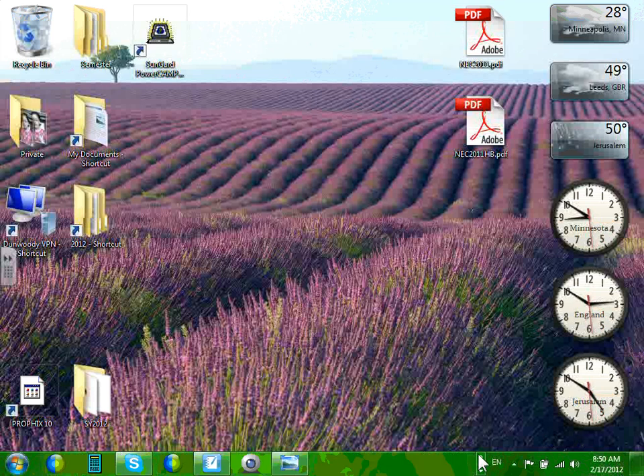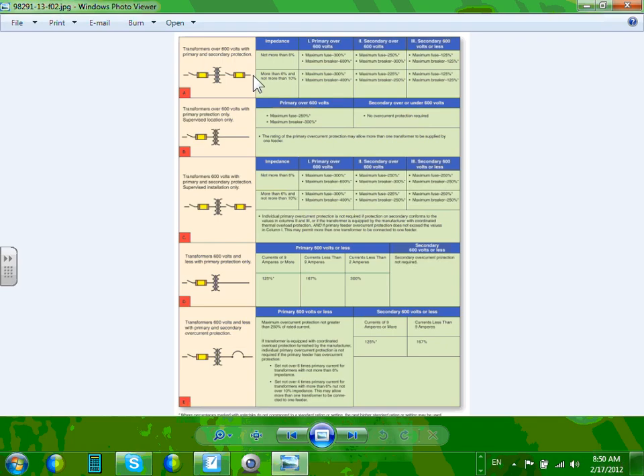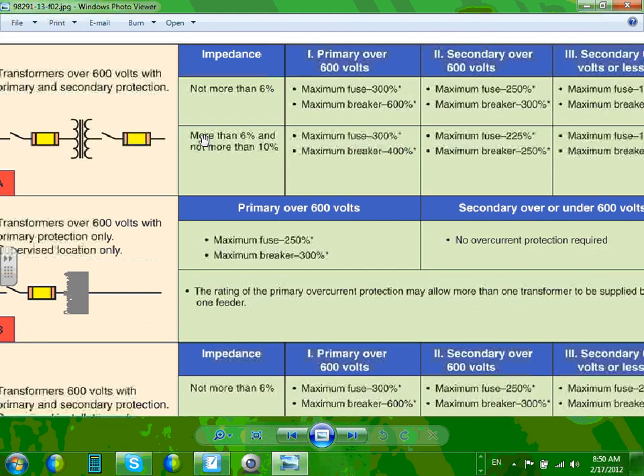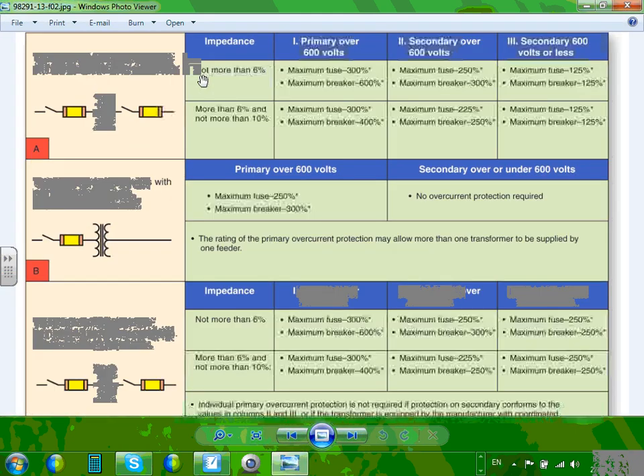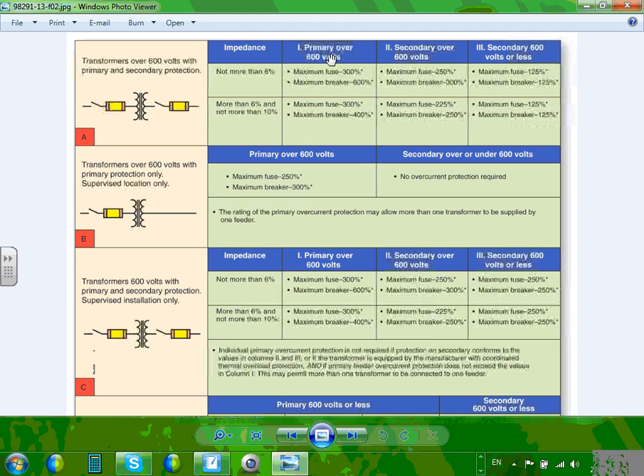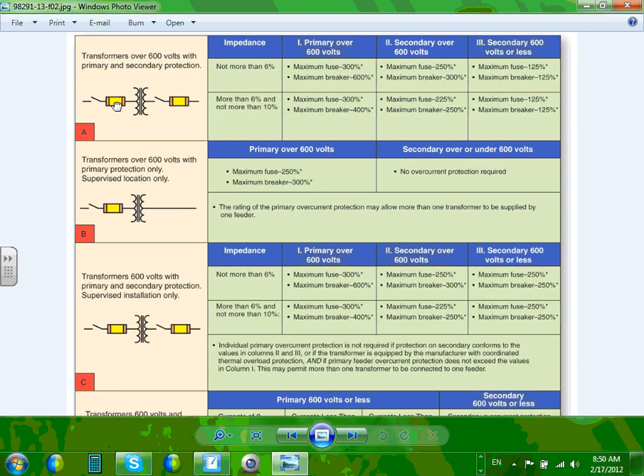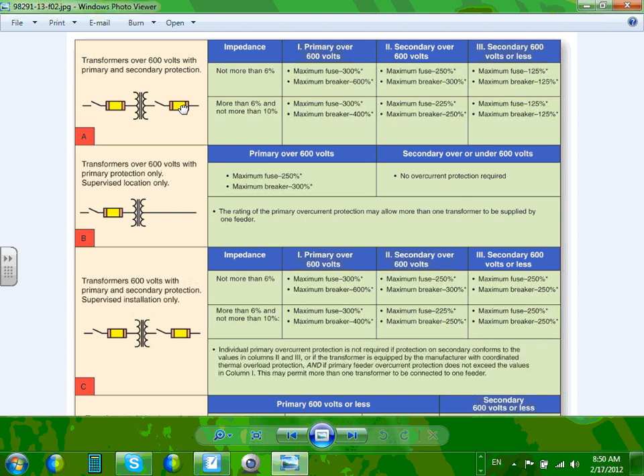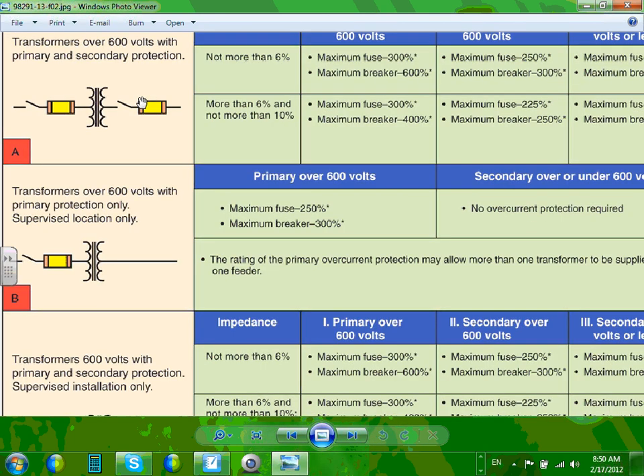While it's powering here. So while it's powering, guys, I want to bring to your attention, when we have a transformer that we have control over, we need to size the primary overcurrent device for the transformer. Do you remember how we did that? We will be doing it next quarter too. The secondary overcurrent device, the secondary feeder, and the primary feeder, as well as the transformer.